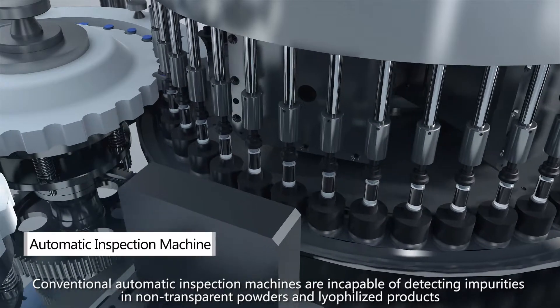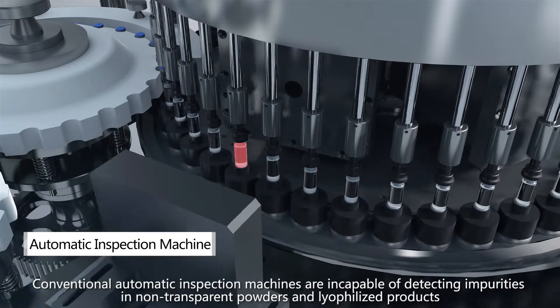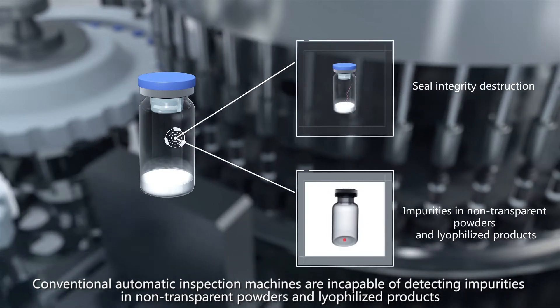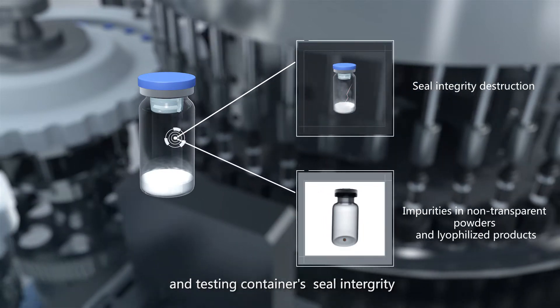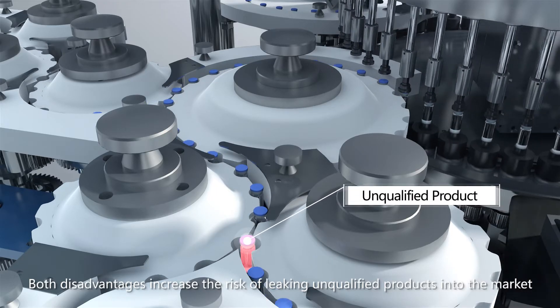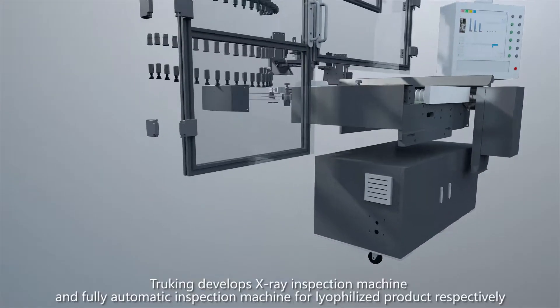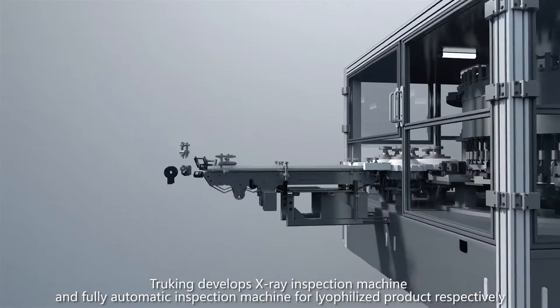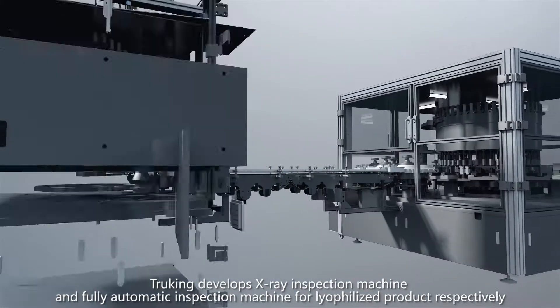Conventional automatic inspection machines are incapable of detecting impurities in non-transparent powders and lyophilized products and testing container seal integrity. Both disadvantages increase the risk of leaking unqualified products into the market. To address these problems, TruKing develops an X-ray inspection machine and a fully automatic inspection machine for lyophilized products respectively.